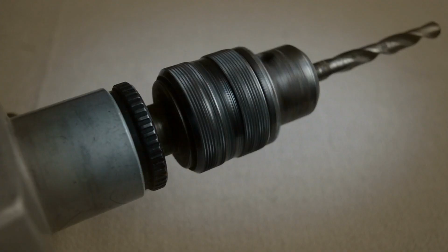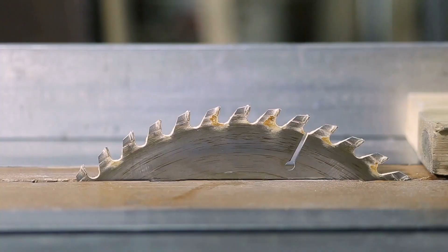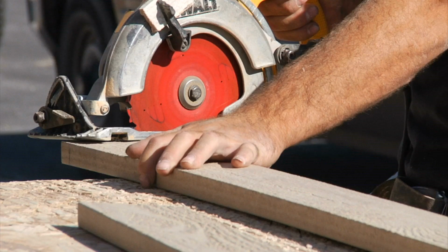Remember, any electrical tools that you are using must be in good working order, PAT tested and either battery powered or 110 volt centre tapped earth supply operated. 230 volt supply operated tools shall only be used due to valid technical reasons. The use of such equipment shall be agreed and documented with an estate's competent person prior to any use. Any essential 240 volt equipment must only be used with a residual current device to guard against electrical shock.